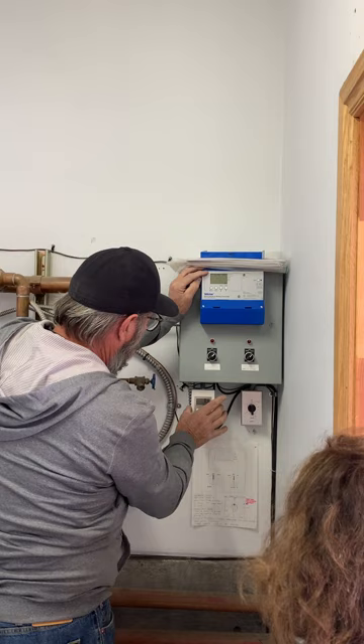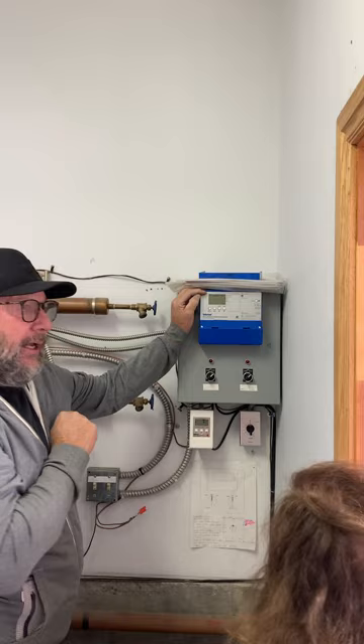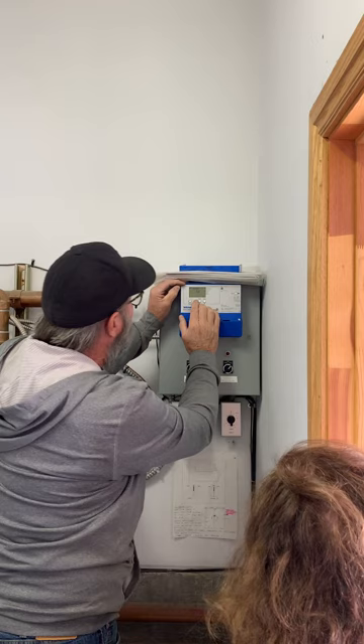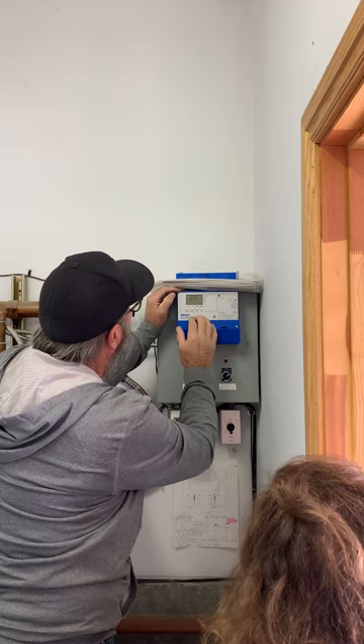Okay. Slab target, what's your target temperature? What are you aiming for? Because we're in warm weather shutdown, we're not aiming for anything. So it's blank right now. Your slab right now happens to be 56 degrees out there. And we're back to warm weather shutdown.